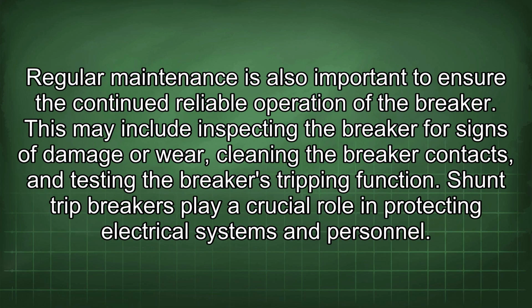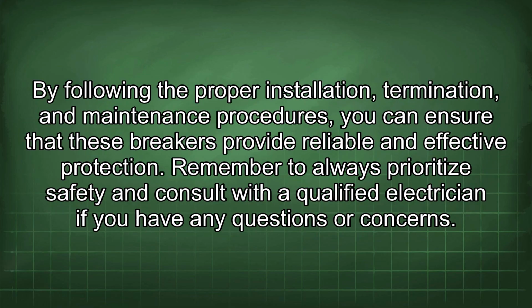Regular maintenance is also important to ensure the continued reliable operation of the breaker. This may include inspecting the breaker for signs of damage or wear, cleaning the breaker contacts, and testing the breaker's tripping function. Shunt trip breakers play a crucial role in protecting electrical systems and personnel. By following the proper installation, termination, and maintenance procedures, you can ensure that these breakers provide reliable and effective protection. Remember to always prioritize safety and consult with a qualified electrician if you have any questions or concerns.